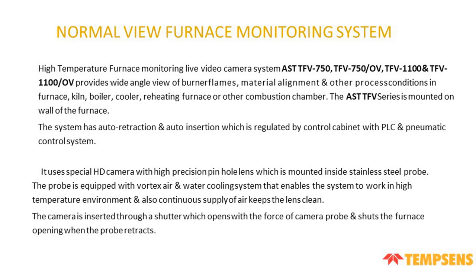The system has auto retraction and auto insertion, which is regulated by a control cabinet with the help of PLC and PCB and a pneumatic control system. It uses a special high definition camera with a high precision pinhole lens tube mounted inside the stainless steel probe. The probe is equipped with a vortex air and water cooling system that enables the system to work in a high temperature environment, and the continuous supply of air keeps the lens clean. The camera is inserted through a shutter which is opened by the force of the camera probe and shuts the furnace opening when the probe retracts.